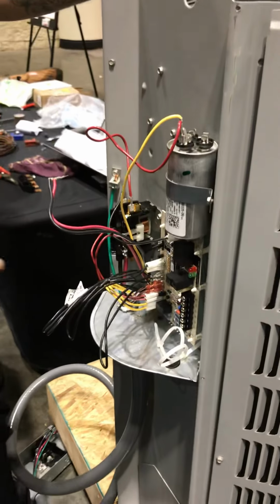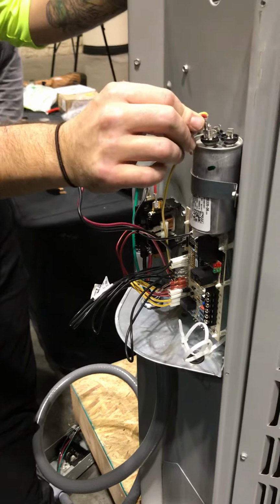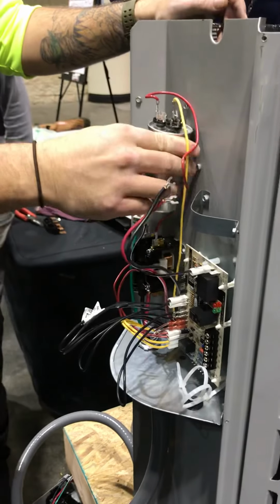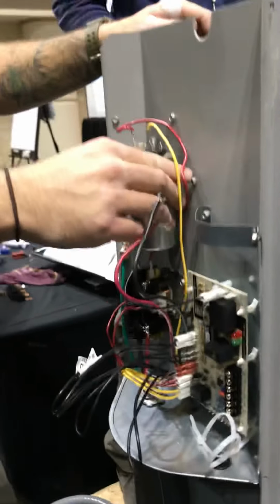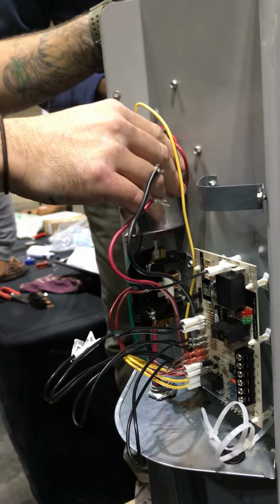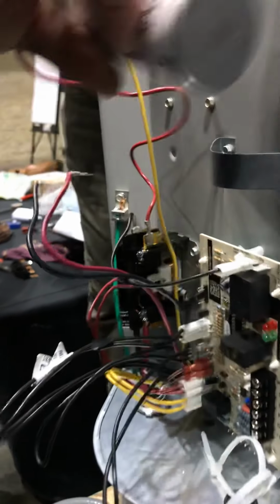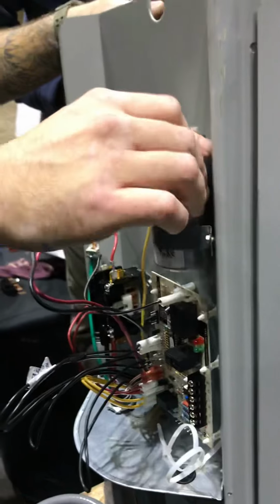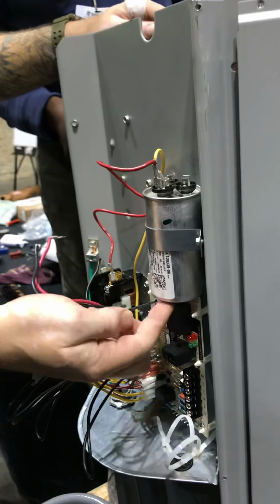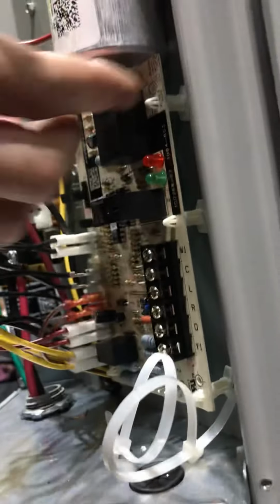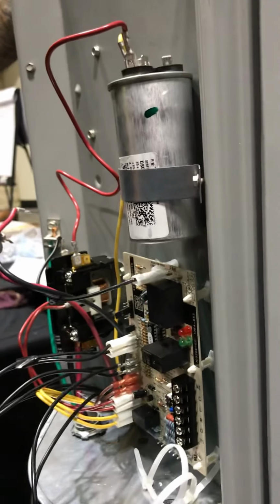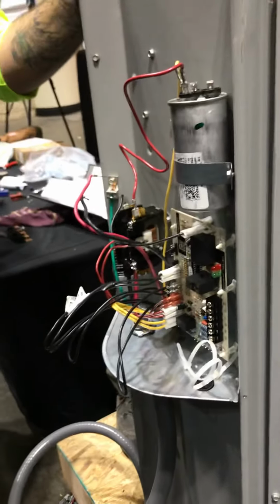And then just double check your wiring. Maybe these 2 wires were touching. That makes sense. Maybe this fell down on top of your contactor. So sometimes this little strap is located right here, and after years and years of it running, it's going to come and touch that. And I've had breakers trip because of that. Or maybe it came down and started touching your fan wire. That's very easily overlooked right there. Maybe it's touching that. So that's just one way to troubleshoot a breaker resetting.